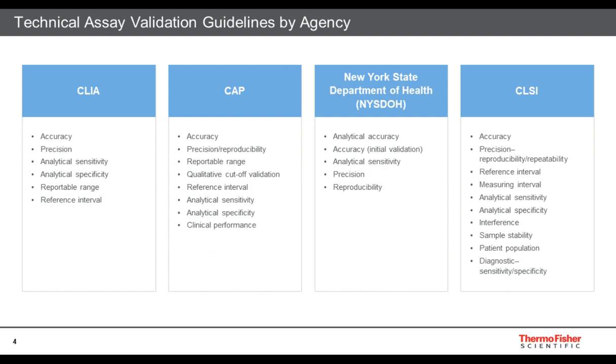The next slide gives the technical assay validation guidelines by agency, including a new player: the New York State Department of Health. What I like to highlight are the commonalities between the different regulatory agencies, especially for analytical validation. Looking at CLIA, CAP, New York State Department of Health, and CLSI, although some have a few more categories, they all focus on covering accuracy, analytical sensitivity, precision and reproducibility, and analytical specificity. I always encourage groups to get the direct requirements and the explanation of what each agency wants to see for each category.